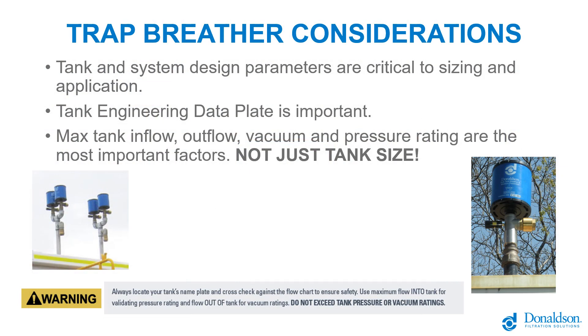For TRAP breather sizing considerations, you need the tank engineering data plate, which provides information such as maximum tank inflow, outflow, vacuum, and pressure rating. It's important to note that it's not just the tank volume that is needed to size correctly. If you have any questions regarding specific geography or local codes, please reach out to Donaldson for additional information.